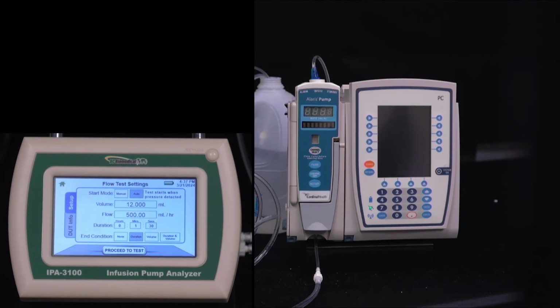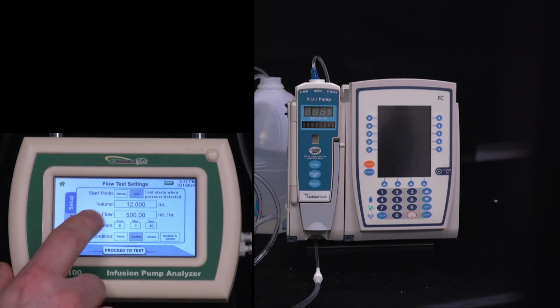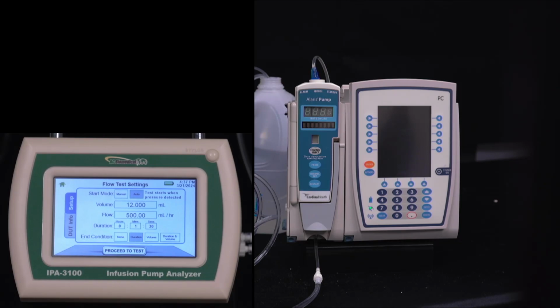So we want those settings to match, because we're going to calculate percentage of error on the 3100 screen. If we want those readings to be accurate, we need to have the right settings. Again, these come from the service manual for the Alaris. They want a flow test at 500 milliliters per hour and 12 milliliters.